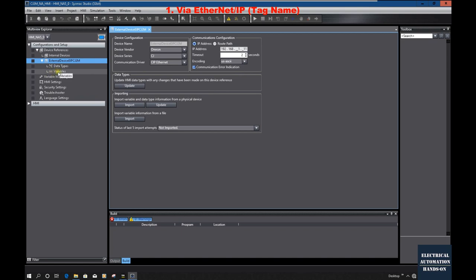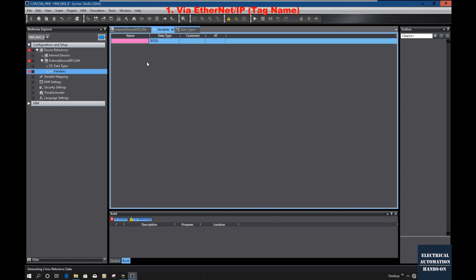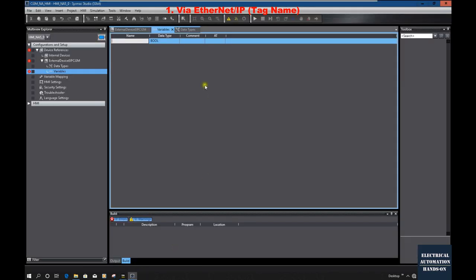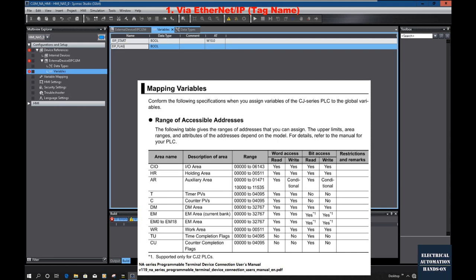After selecting CIP Ethernet and setting the target IP address, we need to set up the tags. From the Variables section, this is the PLC tag area. You can manually add tags by right-clicking and clicking 'New.' The key requirement is that the name must exactly match the name from the PLC side. For example, we set up 'EIP_start' on the PLC side, so we type 'EIP_start' here, with the actual address W10.0. And the next one is 'EIP_flag' with address H500. The names must match exactly.